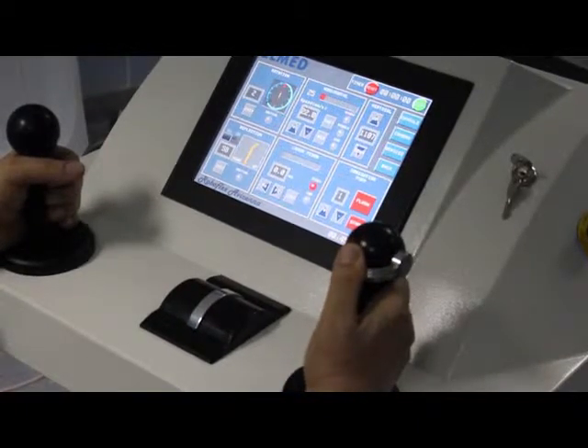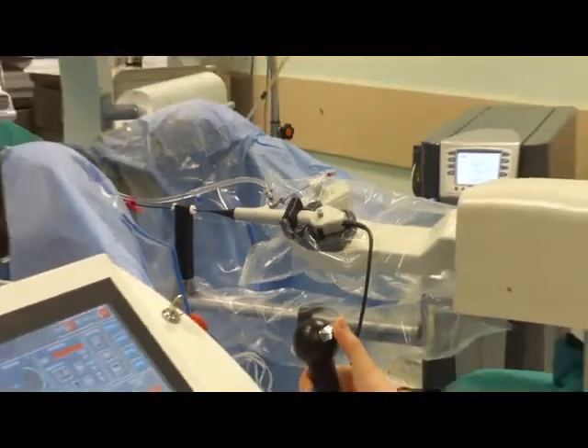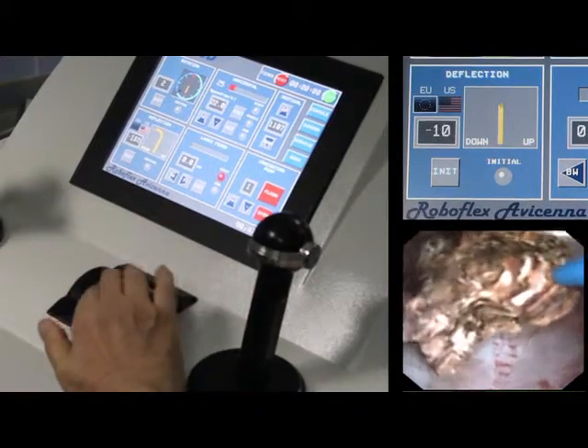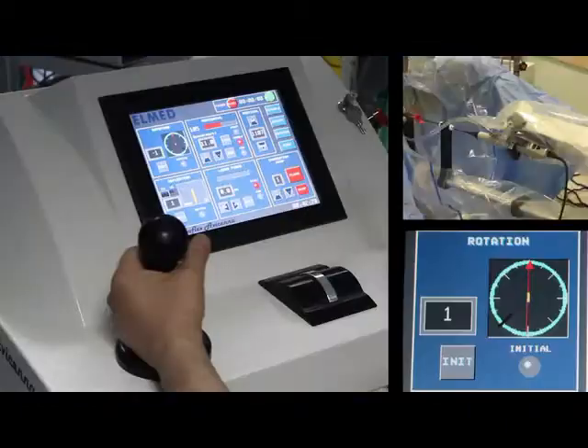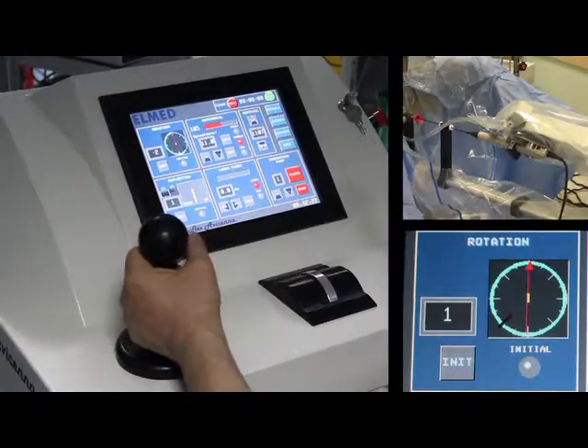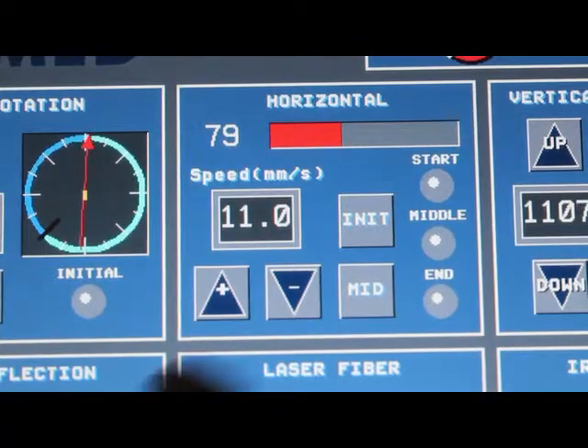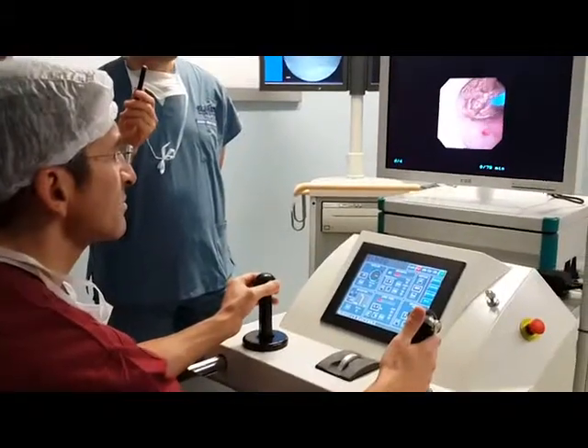Micromotors move the steering lever of the handpiece for fine adjustments of deflection. A central wheel can be used especially during precise systematic ablation of the stone. The left joystick allows for rotation of the endoscope as well as advancing and retracting the scope, with the speed of rotation and advancement regulated on the console screen.